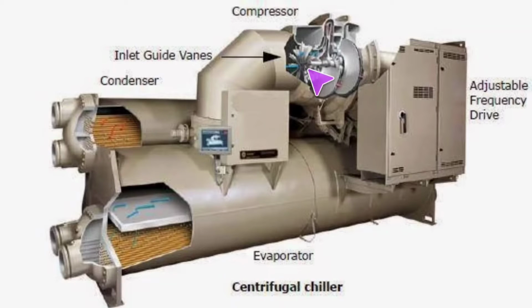Another example, if you're familiar with screw compressors, this is your slide valve, or this is what controls the load. Just end of the day, whatever version of load control you're familiar with, this is how this machine is doing it. It's doing it through these guide vanes. And they'll just close off. They open and close, and they're just as simple as that. They're not a complicated piece of equipment. They do fail. They do have issues, and that's all for another video. But this is what's going to do it.